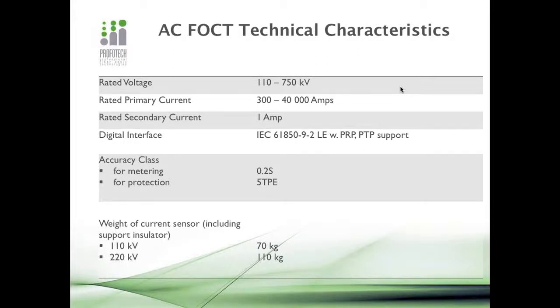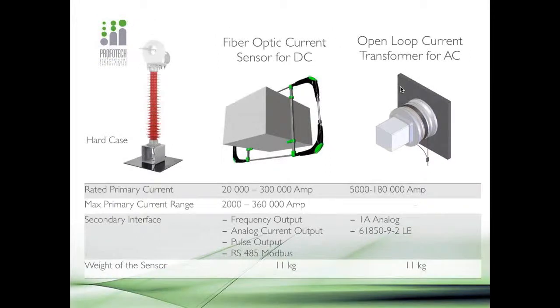So the accuracy classes, by the way, are also shown on the slide, and we have 0.2S for metering and 5TPE for protection. Also, as I said, we can have the fiber optic sensor for DC and AC current, that is the open loop sensor.